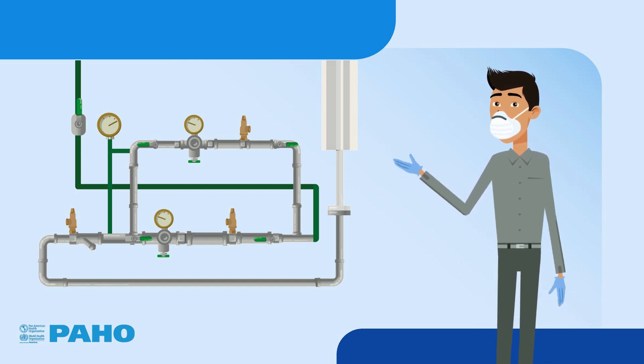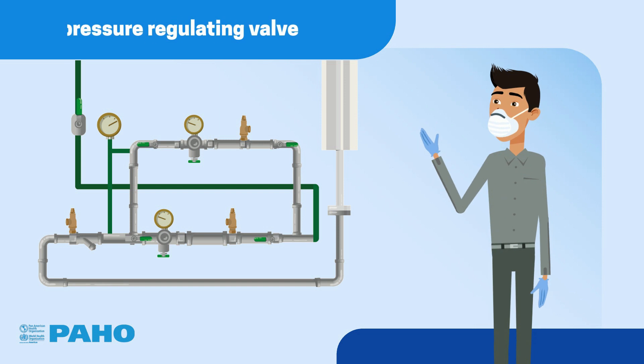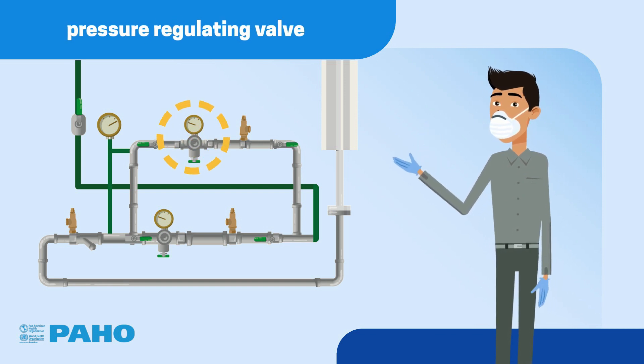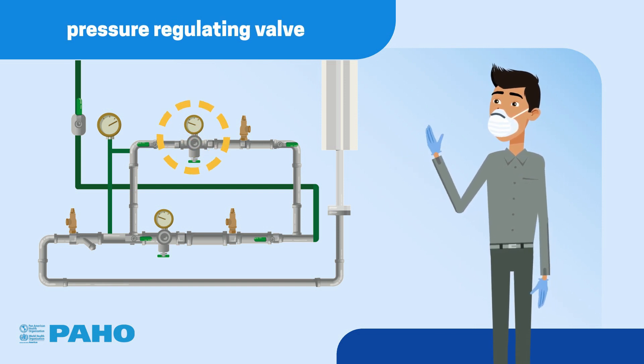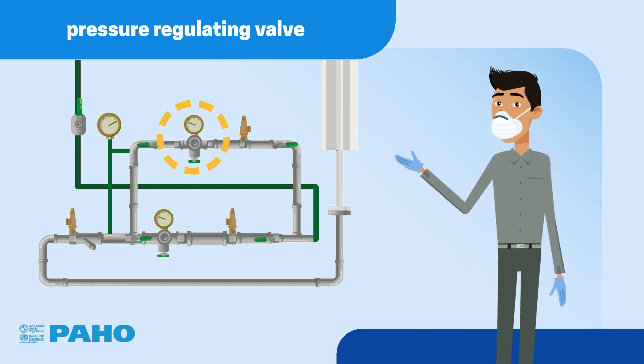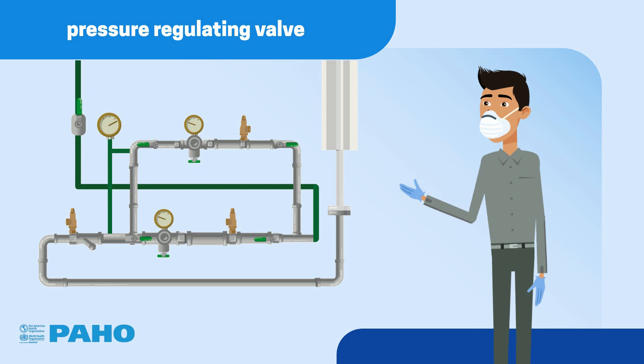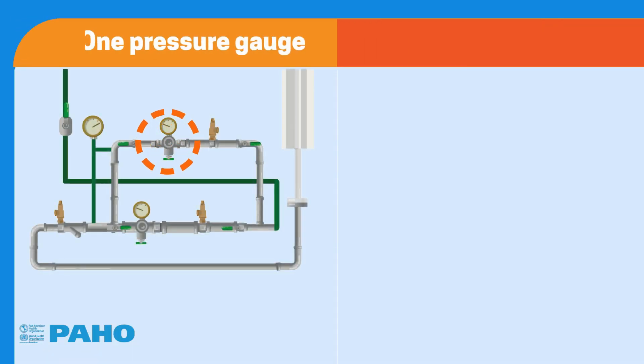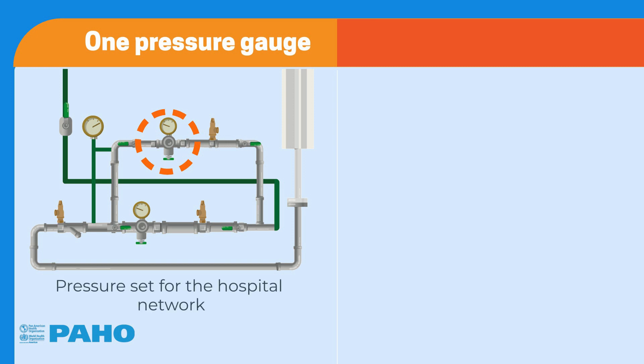To do this, it uses a pressure regulating valve in conjunction with other devices that we will now show you. The regulating valve can have either one or two pressure gauges. When it has one, the gauge indicates the pressure set for the hospital network.